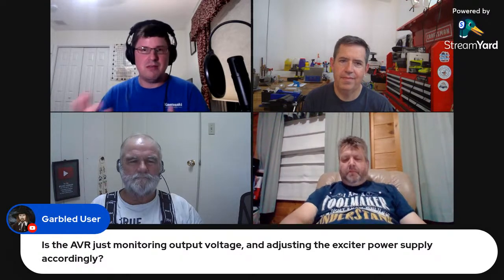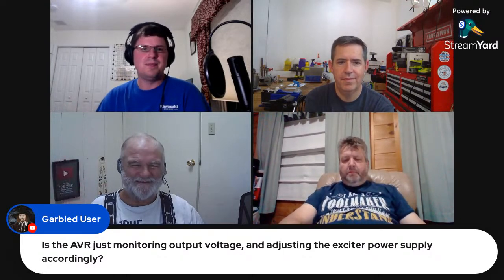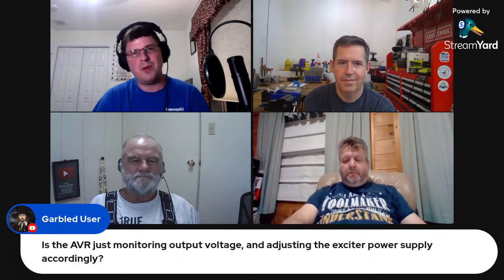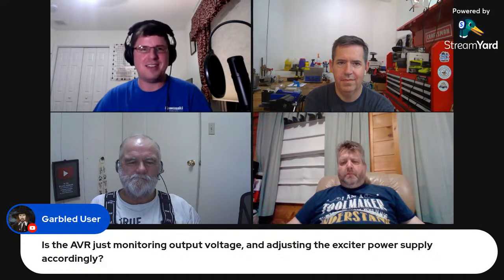And it's the same as any other -- well, it's like a non-adjustable carburetor. That's essentially what it is, and I thought that was kind of cheesy because ideally, in a capacitor-excited generator, the speed determines the output voltage. That's my biggest complaint. Well, and you could adjust it if you change the microfarad rating of your capacitance. So if you go 5 microfarads higher or lower, it'll actually have an influence on the voltage. But then you're also going to be decreasing your capacity for that generator because now it's not going to have as big of a reservoir, and it's less efficient. So that's the only thing with it, it's a simpler design.